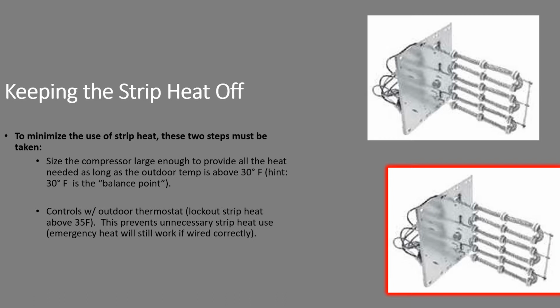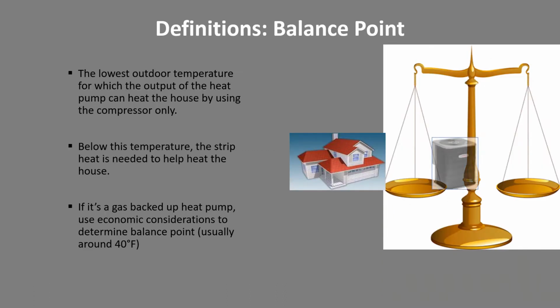It gives you a nice mix of capacity and a nice mix of efficiency and a nice happy homeowner that isn't freezing when it gets cold outside. In order to do this, we have to size correctly. And notice that we call the lockout strip heat at 35. That gives you sort of 5 degrees of flexibility, if you will. If you size for 30 and keep the strip heat off at 35, you'll avoid unwanted customer complaints. Definitions, let's just talk about balance point here a little more. It's the lowest outdoor temperature for which the output of the heat pump can heat the house by using the compressor only. Below this temperature, the strip heat might be needed to come on.